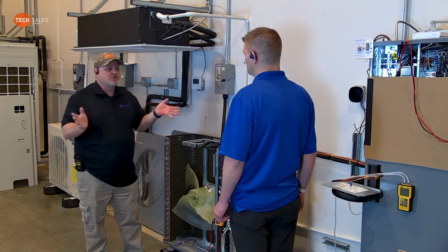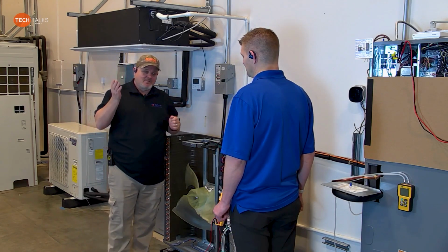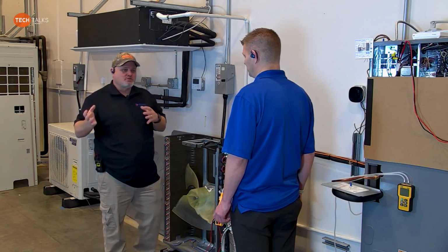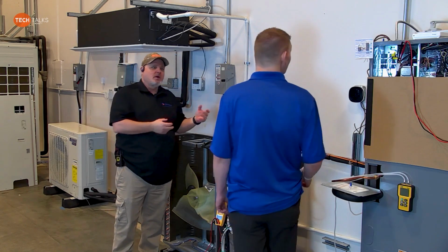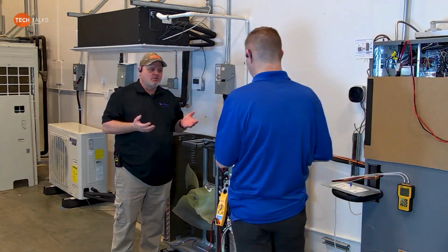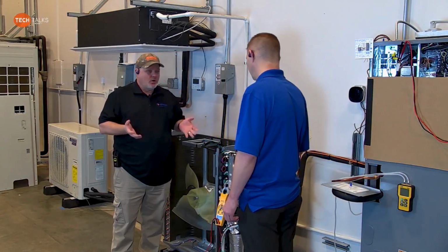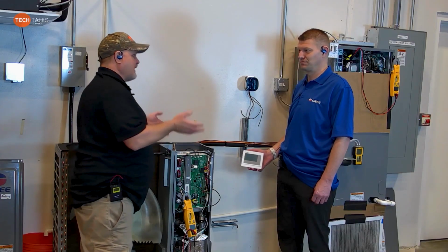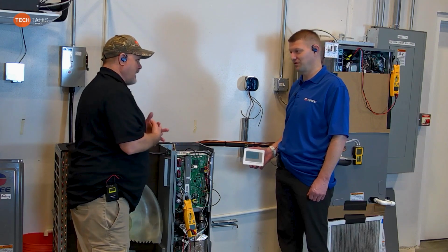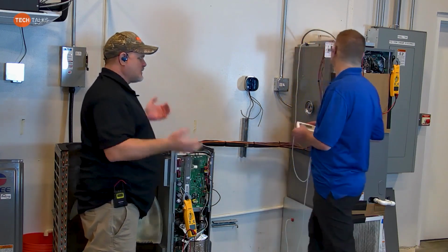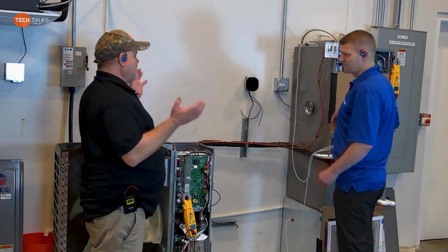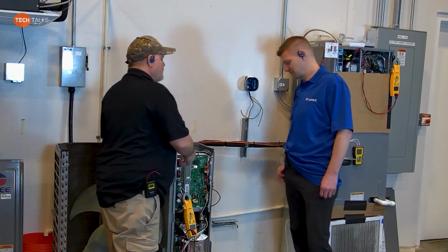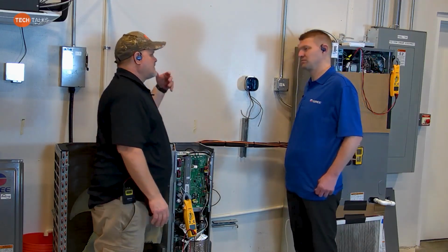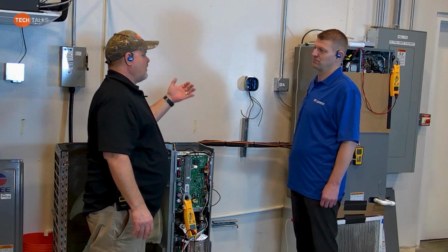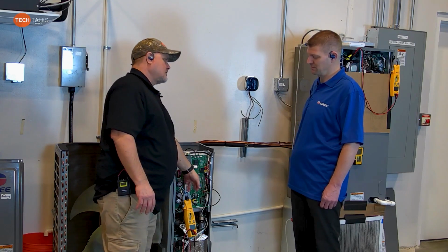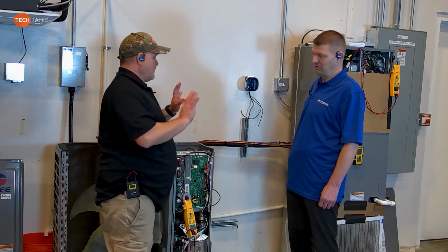Now, factory shipped. As I said at the beginning of this broadcast, we're going to start including the controllers with them. Our first shipment did not include those controllers. But they also come factory set up for our RS485. Correct. So when you get this out of the box and you're going to hook it up with 24 volts, while you've got power off to the outdoor unit and power off to the indoor unit, set SA1 dip switch number 1 to on. Yep. You are good to go.